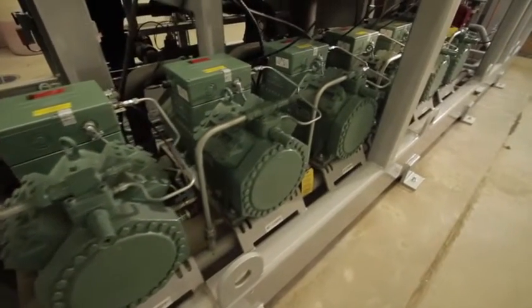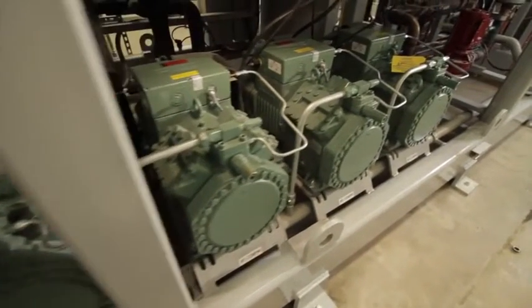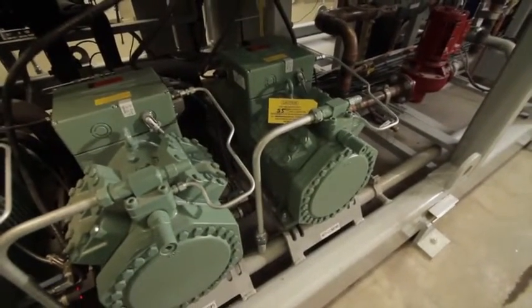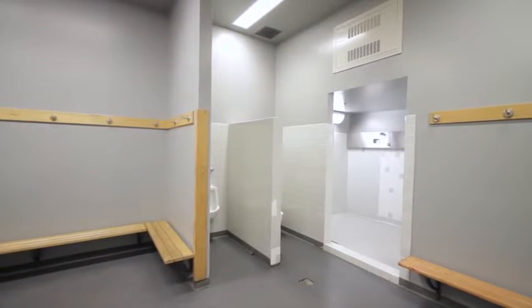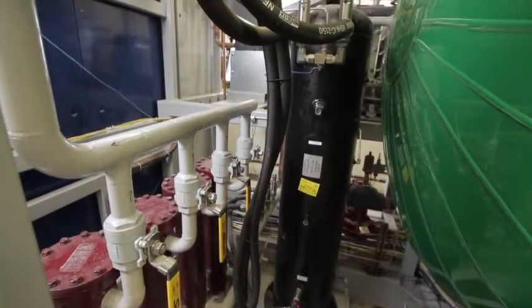Compressors are reciprocating and semi-hermetic, which makes them quiet and efficient. They are fitted with vibration dampers and capacity control ensures precise temperature and ice quality. The CO2 system is a closed system designed for high pressure; it uses up to 90% less pump power compared to traditional systems. The control panel is UL listed and custom manufactured. A two-stage, factory-piped, self-contained heat reclamation system with a glycol pump can use waste or reclaimed heat for space heat, so the locker room, showers, soccer fields, and other parts of the facility feel a direct benefit. Efficient coalescence oil separators and an oil reservoir provide efficient oil separation and a clean system, while the large reservoir capacity adds to lower seasonal maintenance.